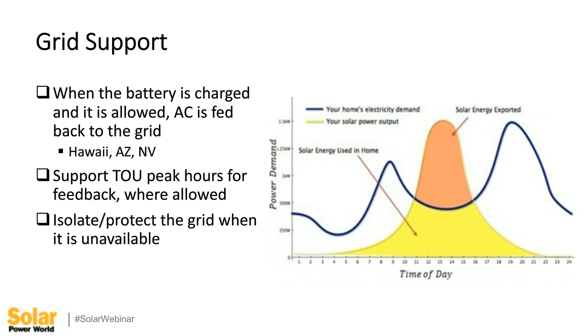You've all heard of the infamous duck curve. If you can store your power during the day and feed it back during the neck of the duck, everybody benefits from that. But having said all that and feeding back, you've still got the requirement of any string or any inverter on the grid to isolate and protect the grid when it's unavailable. You can't feed power back. This is really important to understand: that does not change with a hybrid inverter. You do not feed power back to the grid when the grid's down.